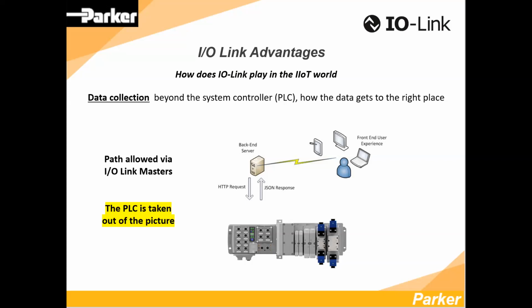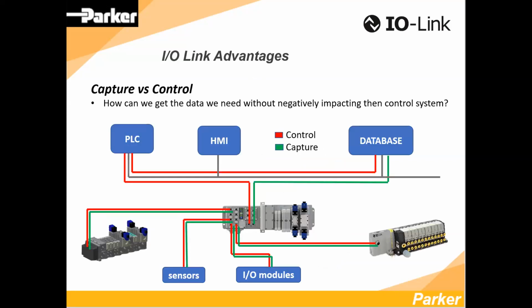So basically this is just kind of a flow. You've got in the upper right there, the database. Now as far as control, he may be doing a build sequence, a production schedule, whatever it may be. He's going to pass that down to the PLC, possibly robots, whatever it might be, but basically to the PLC. Then the PLC comes down to the field bus modules, which is passed right through to the sensors themselves - that's actually controlling the process.